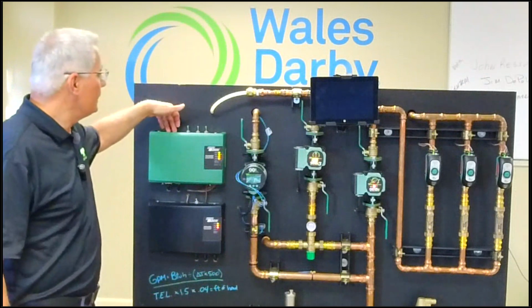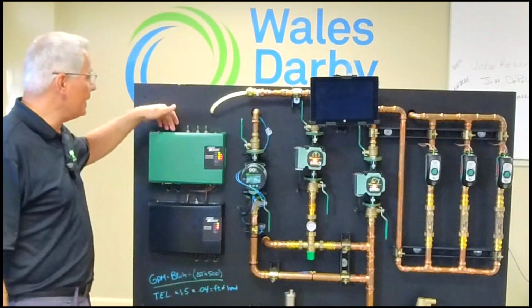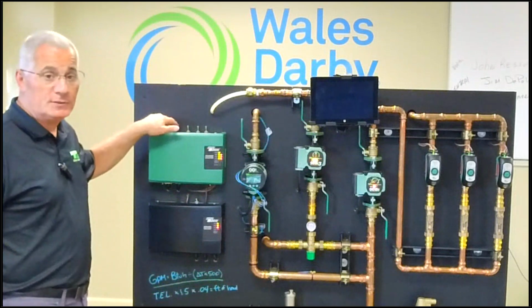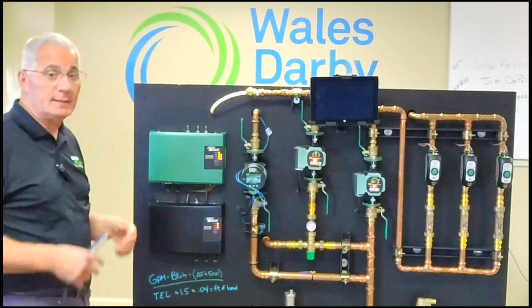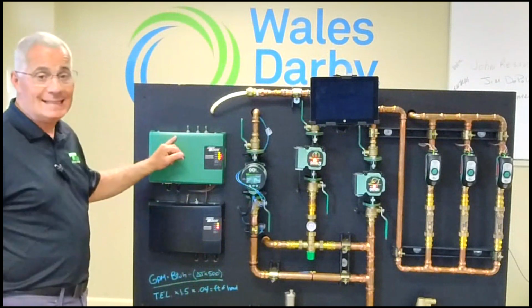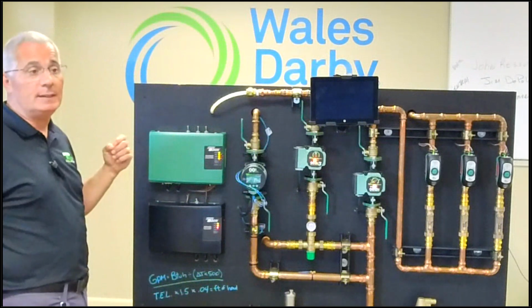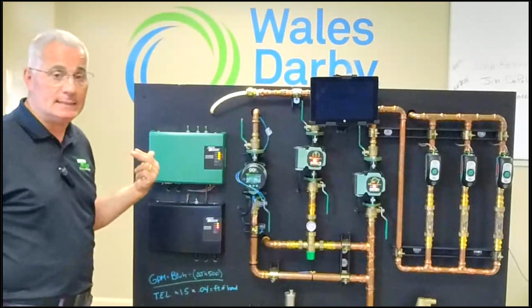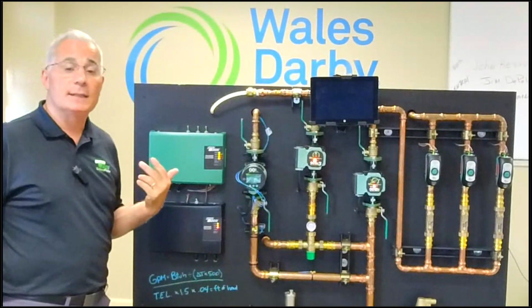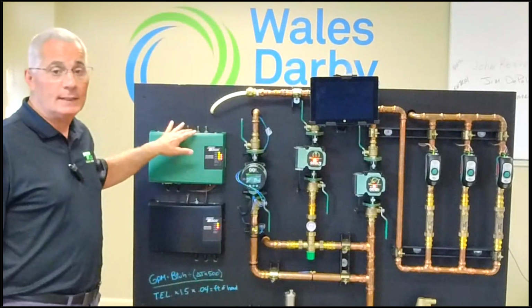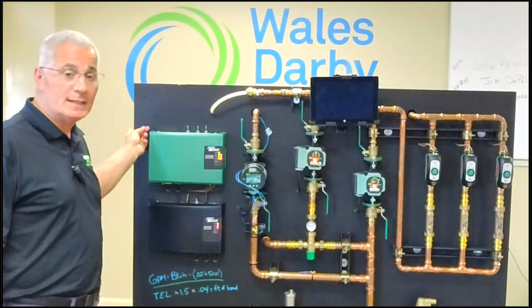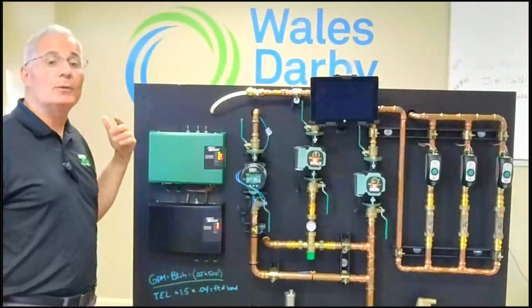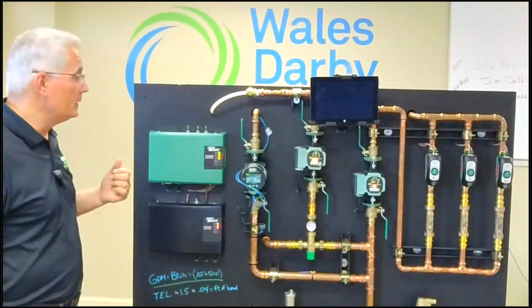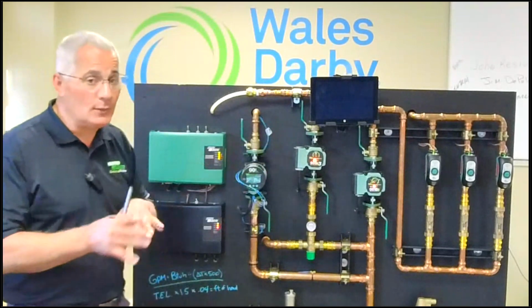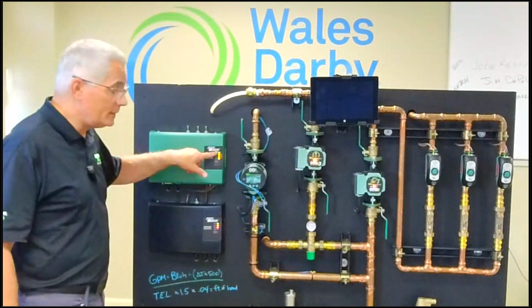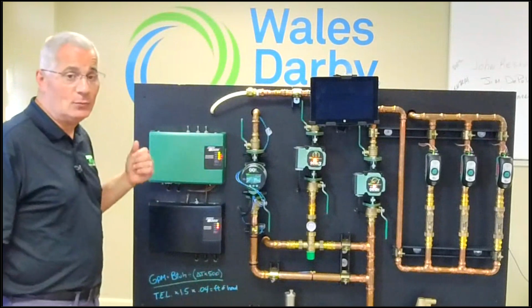Out of the top here, depending on which panel I have, if it's an expandable panel, I'll have 2 end switches. One end switch would just go to the normal TT on the boiler. That's going to tell the boiler to fire. I also would have a DHW end switch here. If that boiler had a second TT just for domestic, let's make believe it was condensing and I wanted to use one of these panels, I would have that DHW end switch go to the boiler's DHW TT to tell the boiler I need you to high fire because we're making hot water. So very neat and clean wiring. The bird's nest disappears. And again, with the lights, anybody can tell you what the system is doing.